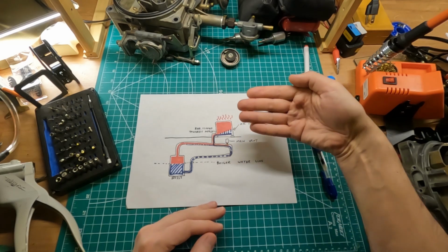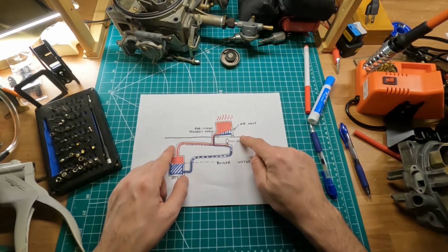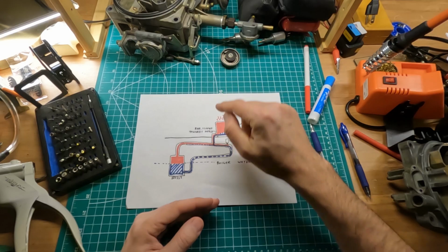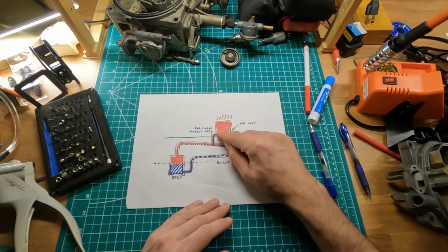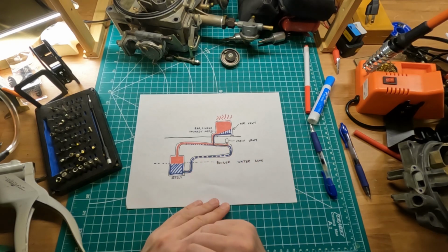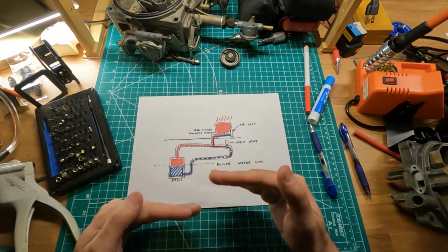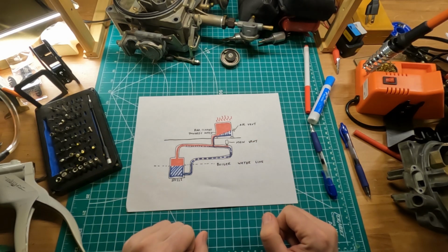So the radiator is not actually perfectly parallel to the floor of the space. It's actually pitched towards this opening, so that the condensate can easily flow out of it back into the main pipe and then back into the boiler. And that's the fundamental, very simplified basics of how steam heat works inside a residential building.